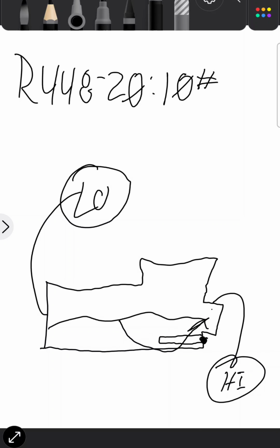So what happens over time is that system gets dirty, rack gets dirty, people don't braze with nitrogen, or whatever it is, which I'm not saying you should braze with nitrogen on a rack, because I don't believe you should, but that's a conversation for a different time. The rack gets dirty over time. This oil is going through that screen, and this screen is doing its job and catching all those particulates, right?